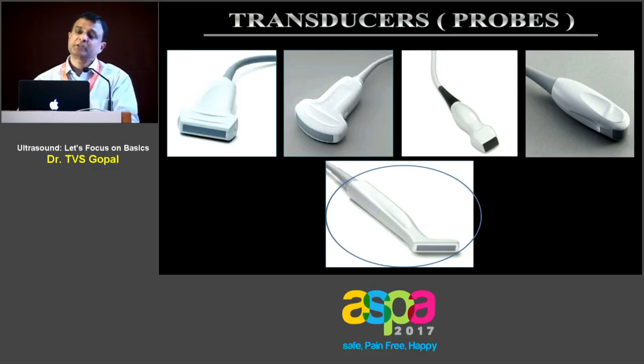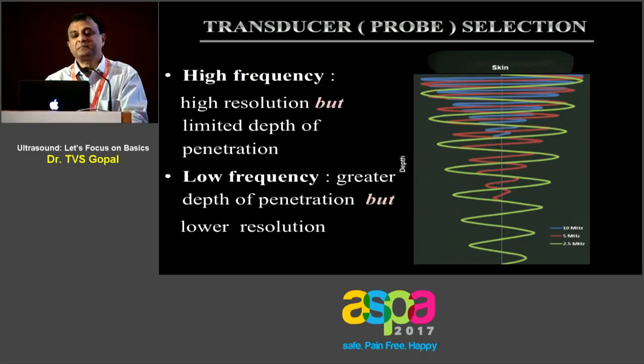These are transducers or probes, and of interest to us is the transducer that is at the bottom, and for obvious reasons, this is called the hockey stick probe. And this lends itself to pediatric applications owing to its very small footprint. Basically speaking, there are two types of transducers. A high-frequency transducer, which gives you a very good image, but the depth of penetration of high-frequency waves is limited. On the other hand, a low-frequency transducer penetrates much deeper into the tissue, but the quality of image that you get with a low-frequency transducer is not very good.